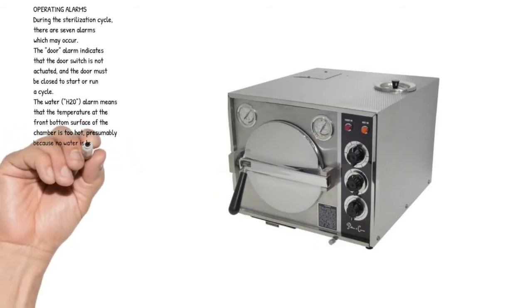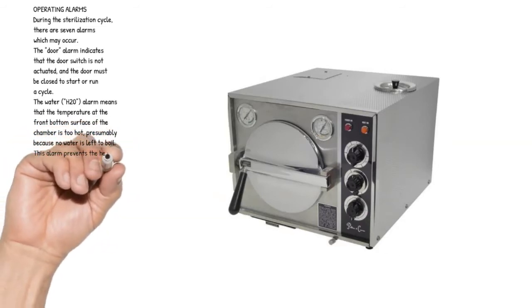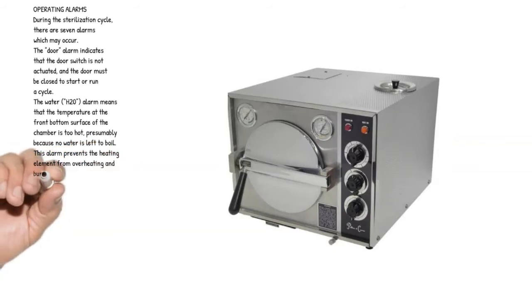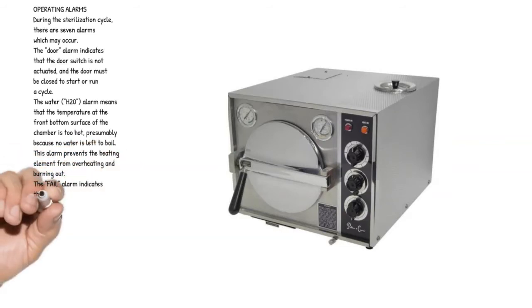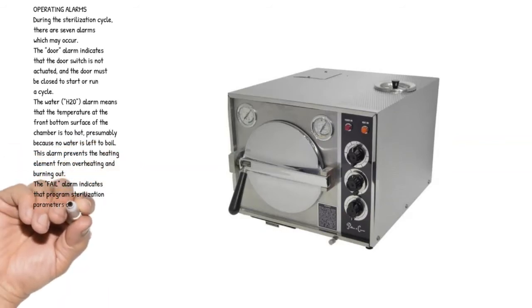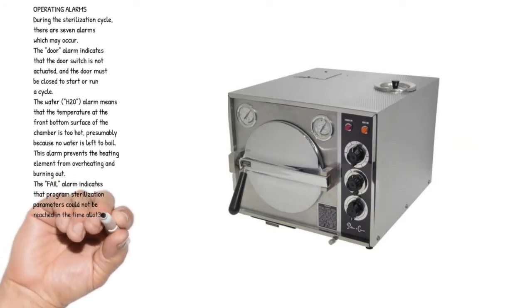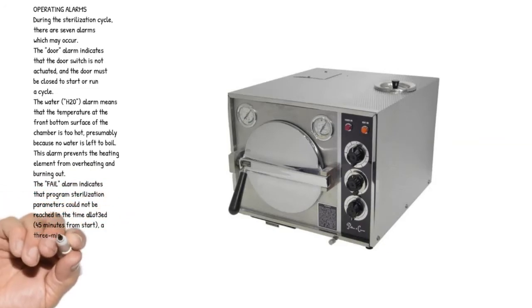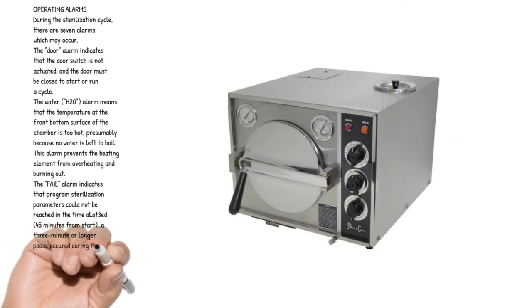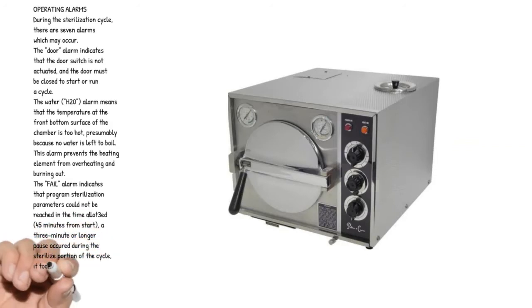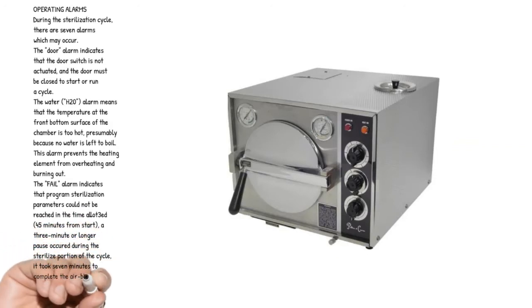too hot, presumably because no water is left to boil. This alarm prevents the heating element from overheating and burning out. The fail alarm indicates that program sterilization parameters could not be reached in the time allotted, 45 minutes from start. A 3-minute or longer pause occurred during the sterilize portion of the cycle. It took 7 minutes to complete the air bleeding process, or the door was opened after fill cycle was finished.